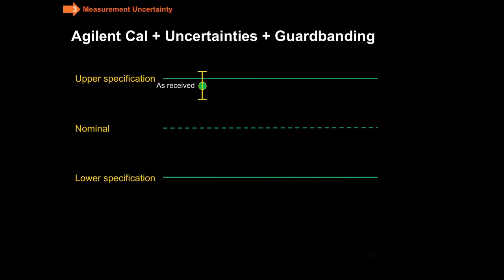Now you might have noticed there the Agilent Cal plus uncertainties plus guard banding. I can show you diagrammatically what that means. Suppose you have a measurement, as received, which is inside the specification, but a portion of your uncertainty interval goes outside of that specification. Well, the little area there in red represents the risk that the instrument may in fact be out of specification.